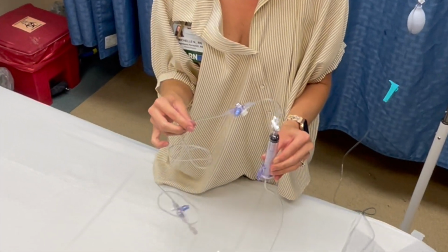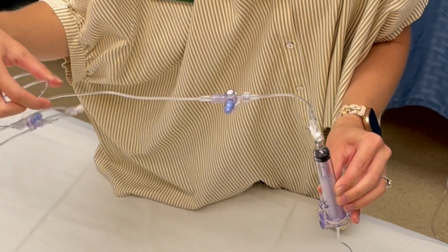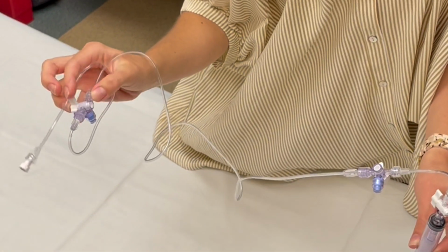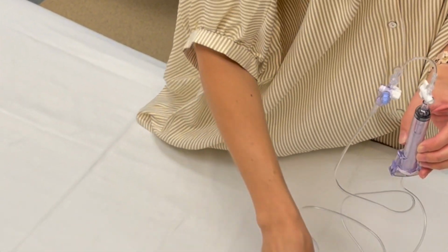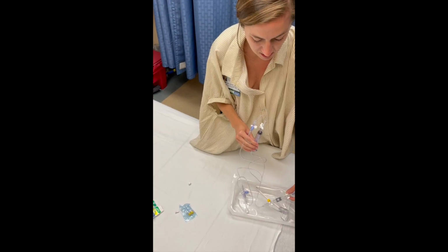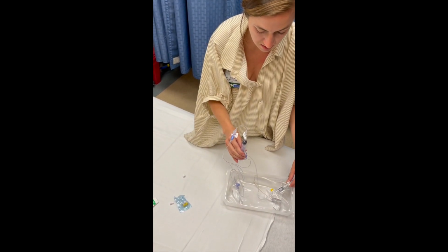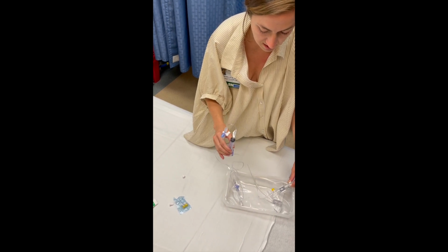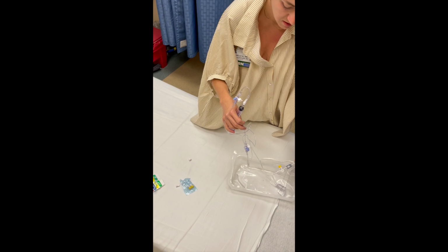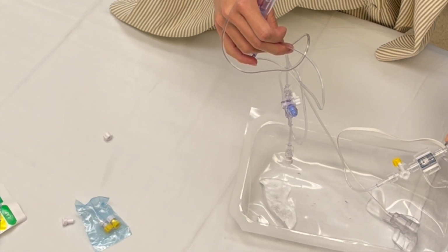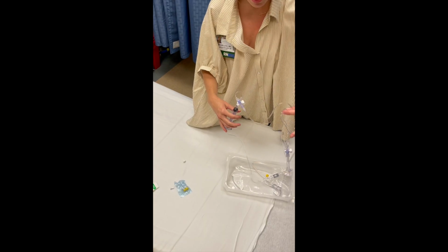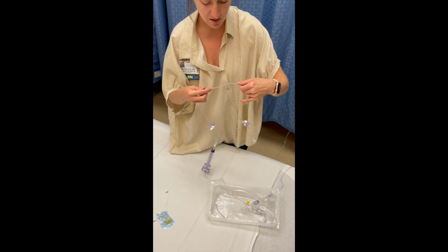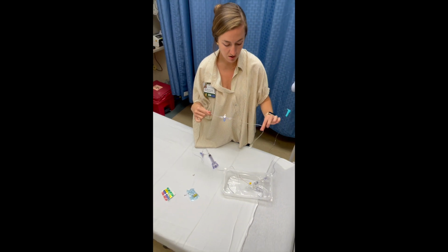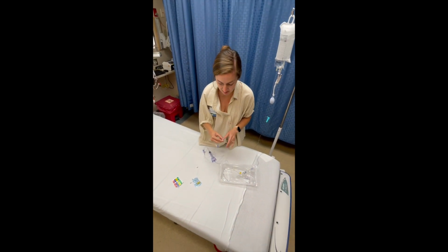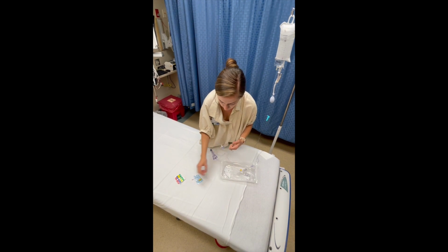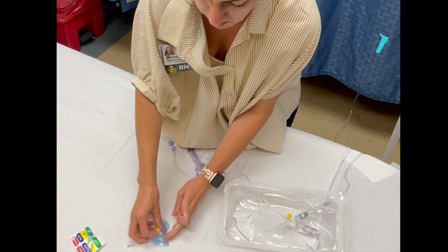For the next step, we're going to have our SafeSet pointed up. The rest of our stopcocks can remain in the neutral position. Again, depressing our flushing mechanism here and waiting until saline comes out of the end of the system. I'm gonna do this for a few seconds and then visualize on my tubing that there are no bubbles. Lastly, I'm gonna change out my white cap for a yellow cap.